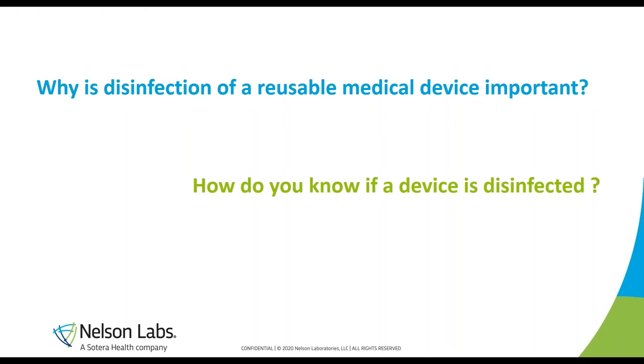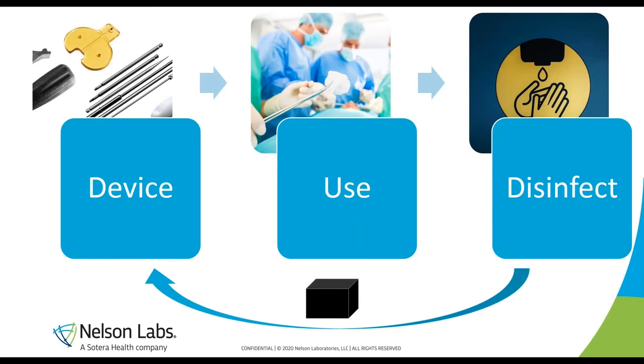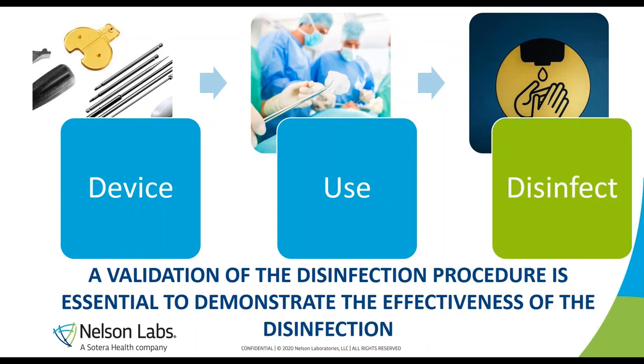If you disinfect your medical device, how do you know if it's disinfected? Can you visually check that? No — you're dealing with what I call a black box. When you disinfect your hands, you follow the procedure and use alcohol gel, but you don't actually know if viruses or bacteria are killed. You rely on the disinfectant and the procedure. In the healthcare facility, you have to trust this black box and rely on the procedure. That's why validation of the disinfection procedure is essential — it's the only way to demonstrate effectiveness, because in the facility there is no further check.